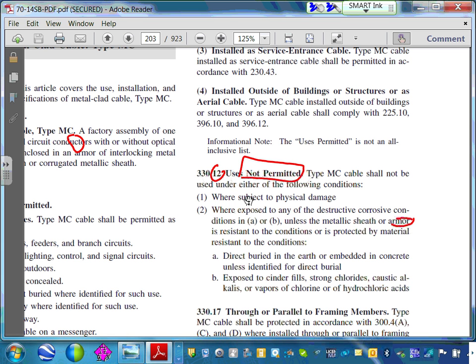If you want to know where you can use any cable, go to .10 or .12. If I ask, is this cable approved for a hazardous location? You'd go check the .12. How about, is MC cable approved where it's subject to physical damage? No. How do you know? It says so right here.